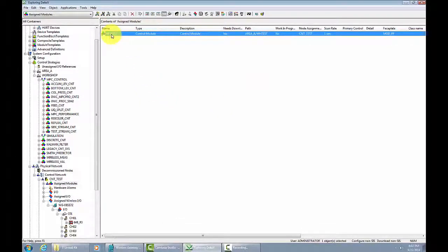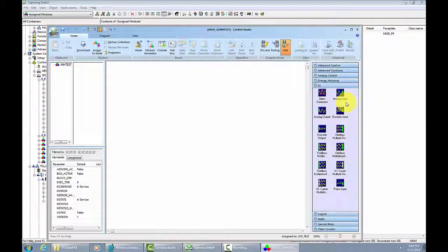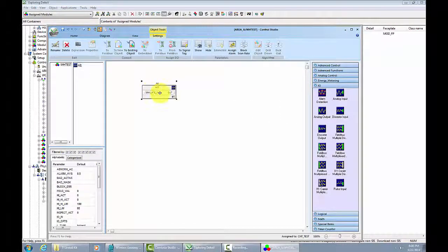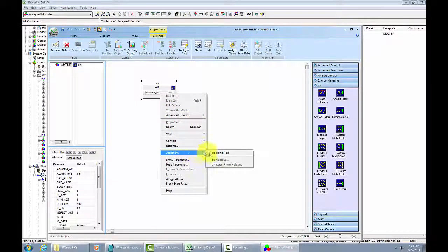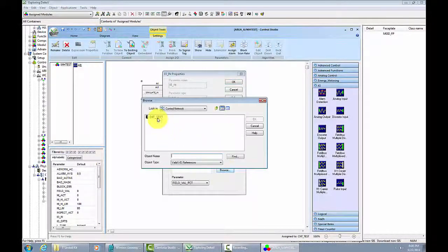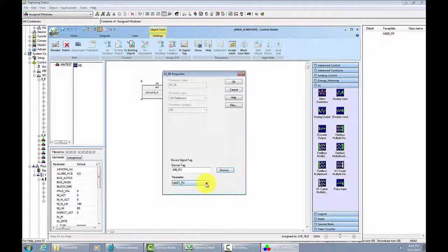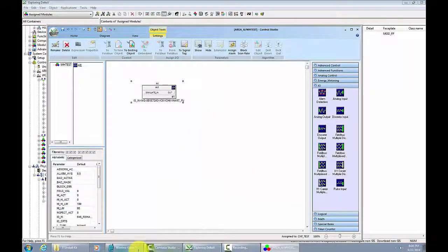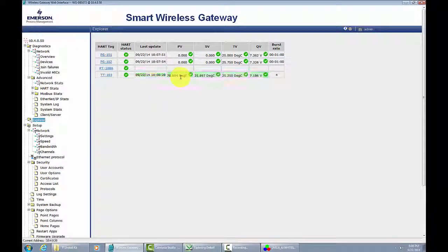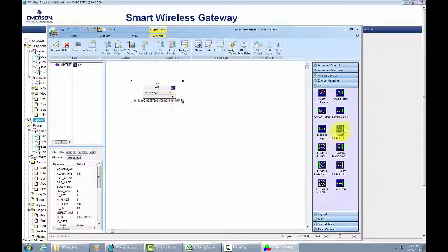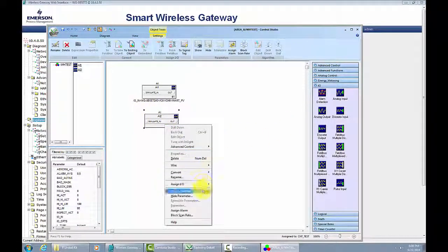We'll open the Control Studio, and we're going to assign. We'll pick an AI block, and we'll assign the PV of the HART device. So we'll first select the device, and then by DST, and then select the PV. We'll also pick one more HART parameter. So we'll go back, so you can see we're communicating PV, SV, TV, and QV. So we'll also look at the TV value. So we'll select that over on the Control Studio. So we'll pick that and again assign it to the HART variable.